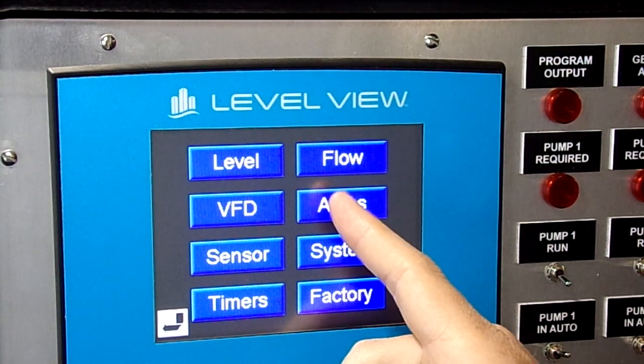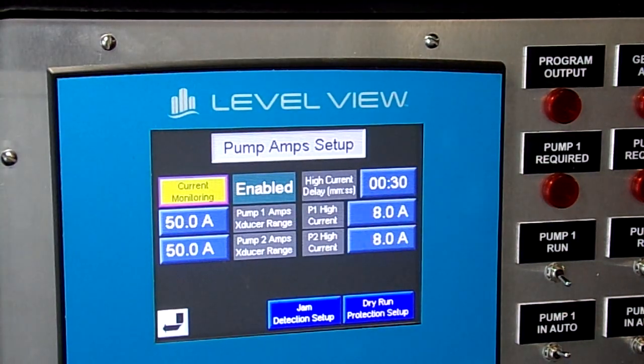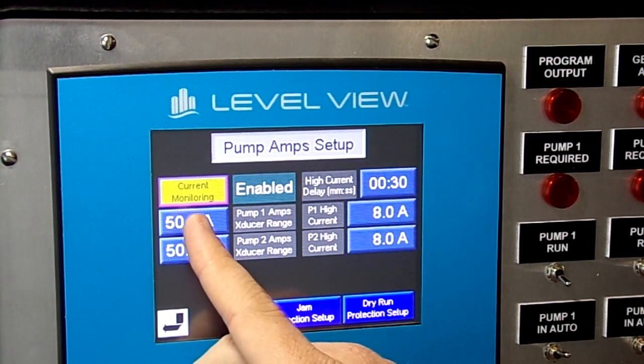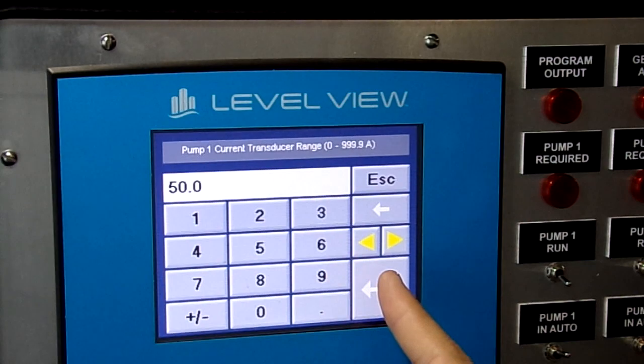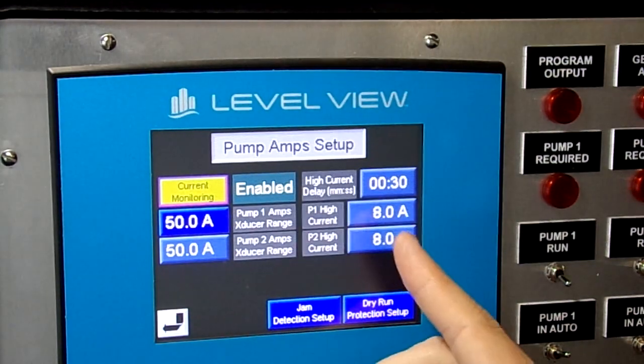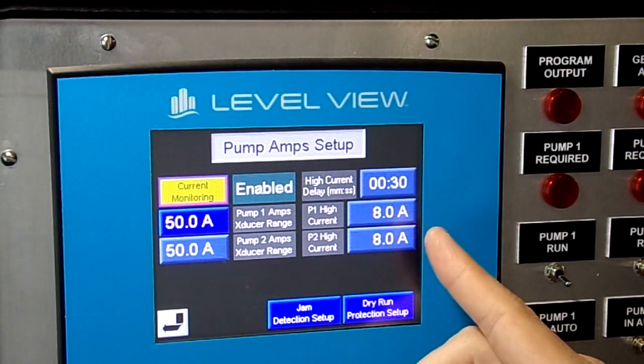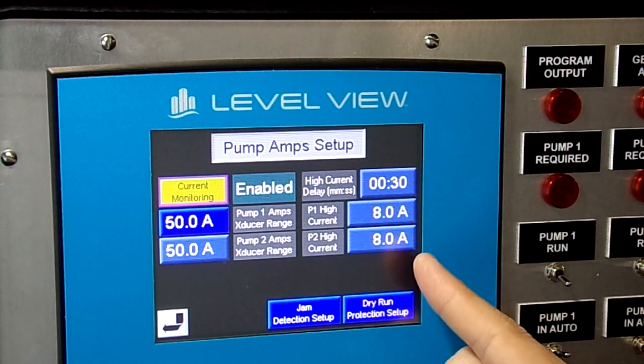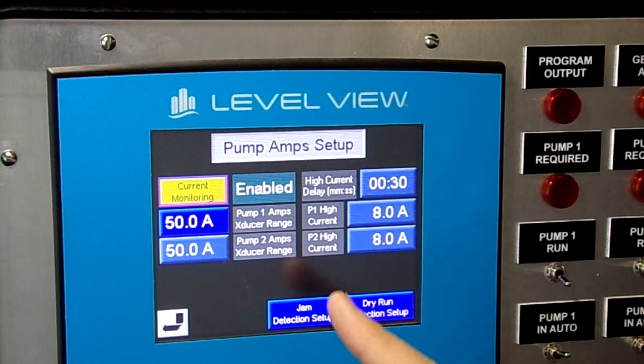For your amps, this is where we will set our current transducers. So a current transducer will have a set range that needs to be inserted here. This one is set for 50. Your high current will need to be set for your pumps. So your pumps will be 8.0 on this particular station, which will help set up our jam detection setup.